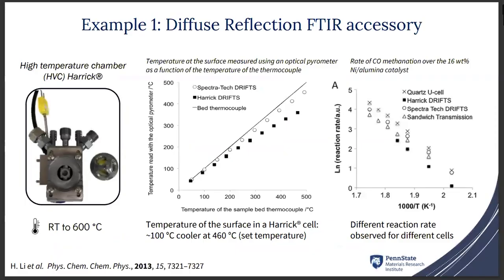So the first example is the diffuse reflectance high temperature chamber from Harrick that allows to do reaction or analysis of material from room temperature to 600 degrees Celsius. And it was pointed out in the literature that there is a drift of temperature between the temperature recorded at the sample bed thermocouple and the actual temperature on the sample. So this temperature drift can be up to 100 degrees Celsius at a 460 degrees Celsius set point. So this analysis is just made by the temperature you set on your controller versus the temperature recorded with a pyrometer.